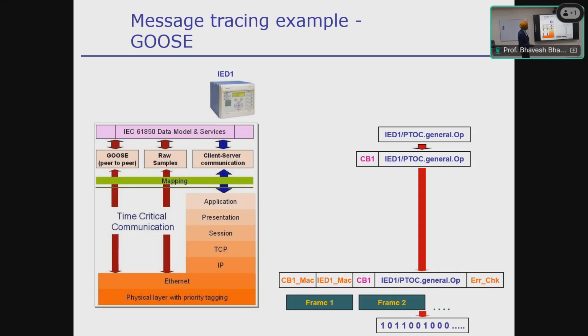IED1 is going to issue the trip command. So IED1 protection general operation, it's for circuit breaker 1, and then it appends the MAC addresses. Basically it appends, and that's it, nothing else. And then we have the frame, which basically goes directly through the link layer.